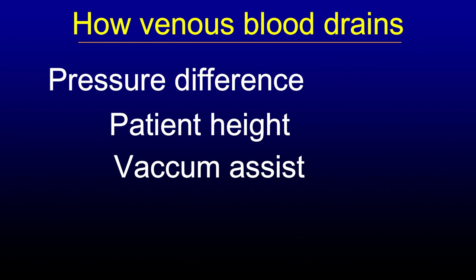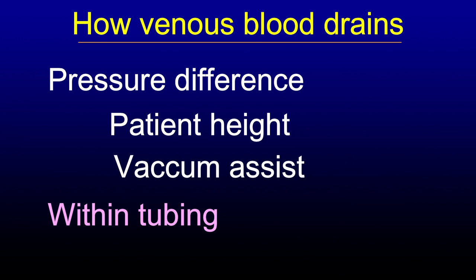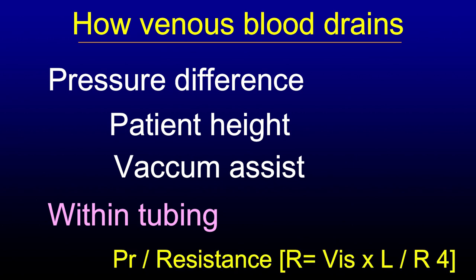The second factor is vacuum assist. If you reduce the pressure within the reservoir by means of vacuum, the pressure difference between the patient and the reservoir increases, thereby increasing the flow from the patient to the venous reservoir. The third aspect is the resistance offered by the tubing. One has to remember Poiseuille's law — resistance is inversely proportional to the fourth power of the radius of the tube. Always keep the tubing length short to have better flow to the venous reservoir.